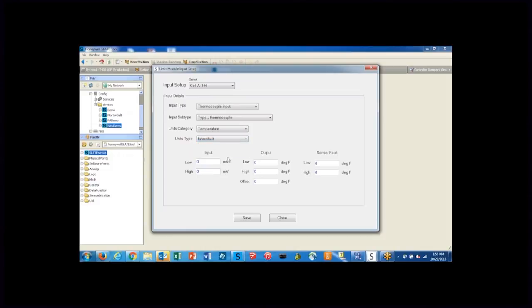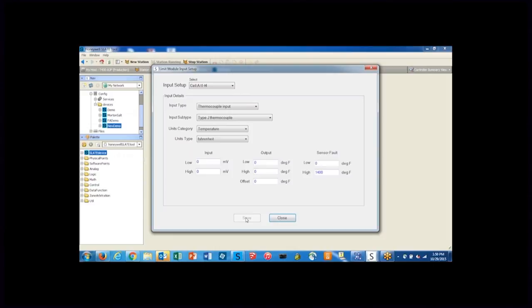You can go through and put different millivolt low and high input settings here as well as some output settings if you're going to output this control signal or this temperature signal and sensor fault. I usually put the sensor fault at 1400 and I will save these settings.